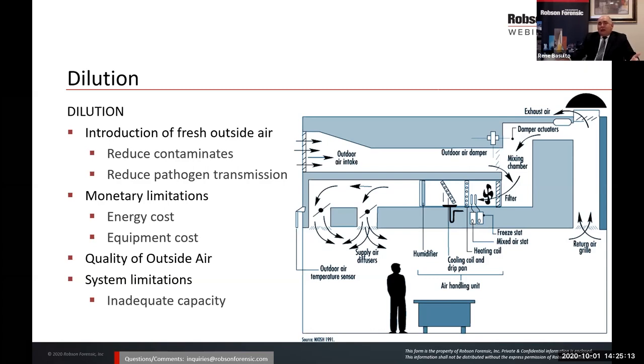And very similar to that, and I've designed hospitals as well. This is a good example because we just finished designing it. We're actually going to start building it through a construction company. It was a design-build project. But hospitals are built the exact same way. Isolation areas and isolation rooms, depending on the type, if it's a contaminant disease isolation room, you want to make sure that the room is under negative pressure so no air from that room goes to the other spaces. If it's a clean isolation room, you want to pressurize that room to prevent any air from coming into it, where it might be somebody who is immune compromised or in a very delicate position that anything could affect them. So there are both ways.